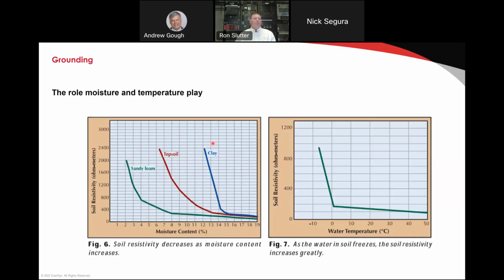If we're in a dry environment, resistivity goes way up. Look at the moisture content. As it goes down, the connections become worse in different types of soil. If water freezes, so here's a very important one. If you put your ground ring in around your building and it's not below the frost line, then when the ground freezes, you lose your ground ring. You've lost your ground because it's not buried below the frost line. So very, very important. Make sure the top of your ground rod and your ground ring are below the frost line. In some situations, that can be very hard to achieve.